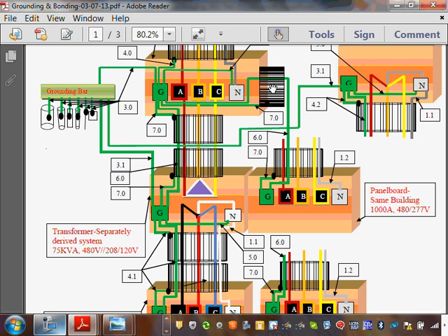Okay, so imagine, now we're focusing on the grounding and bonding. Here's my 1000 amp. I need to pull a conductor right in here. Can you guys see that conductor? It's called 6.0. This conductor is called the equipment grounding conductor. That's typically called the ground. 6.0 is the equipment grounding conductor. Right next to it is 7.0, and the numbers have nothing to do with the code. They're just randomly picked for identification.